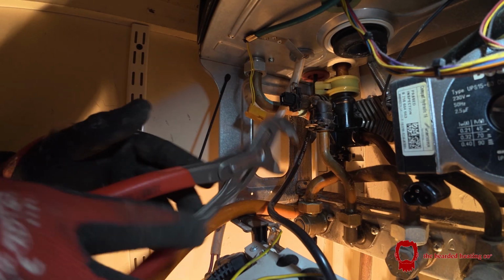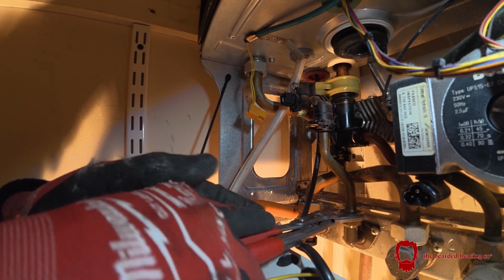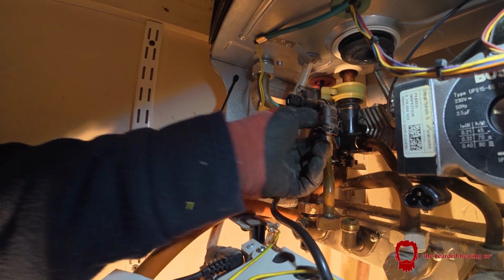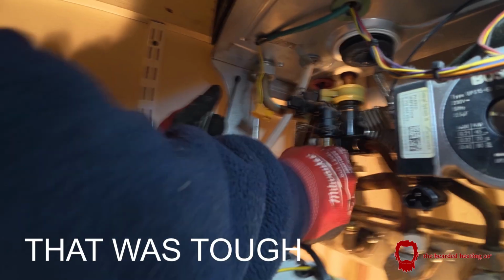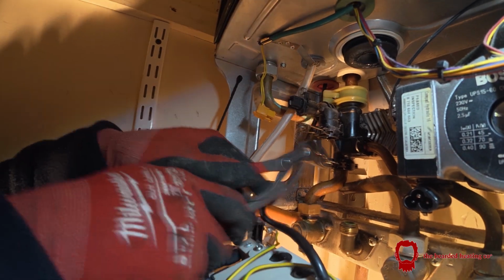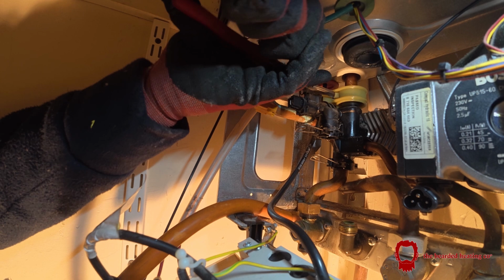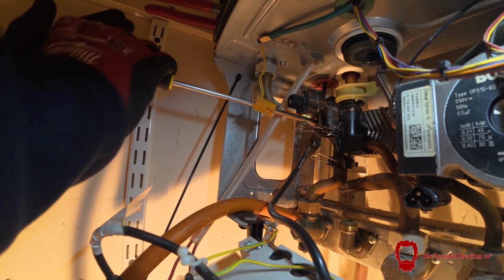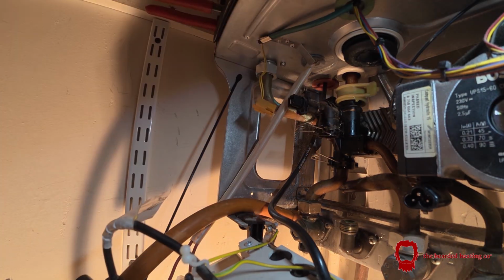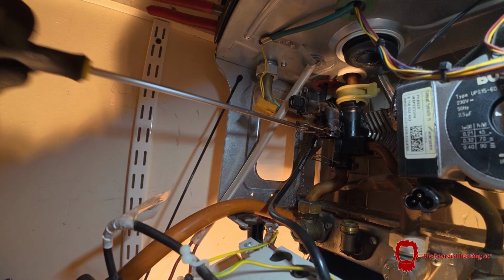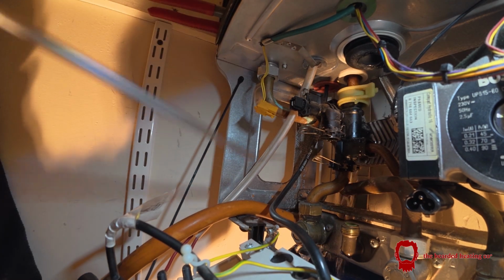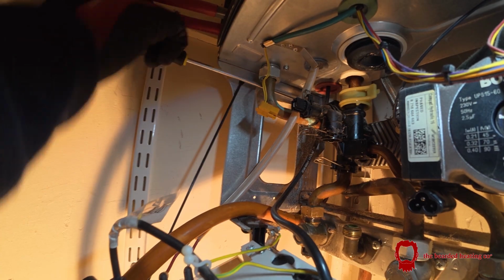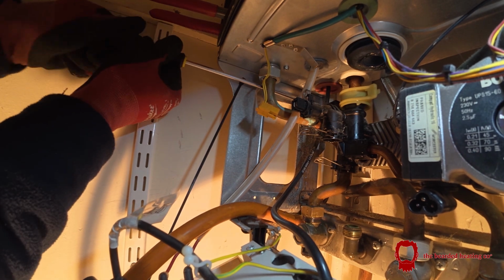Let's crack these open. Might as well get this out because we're going to replace the whole block. Drop the plate heat exchanger. I've got my own plumb tub ready, underneath the plate heat exchanger. Just the one last screw that holds the manifold for the hydro block to the boiler chassis.